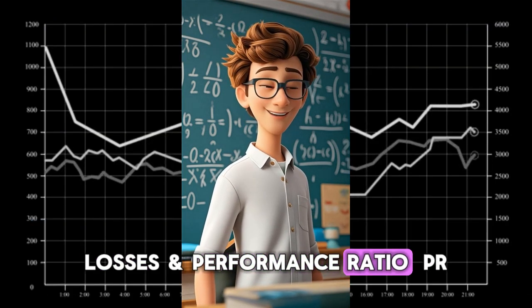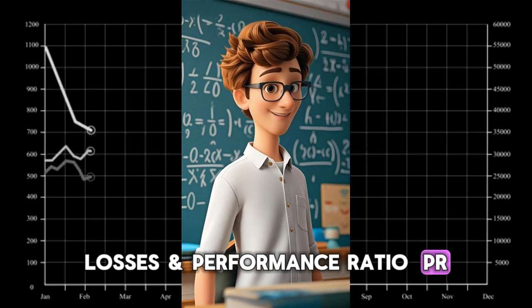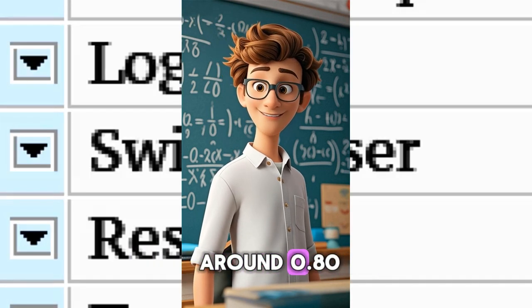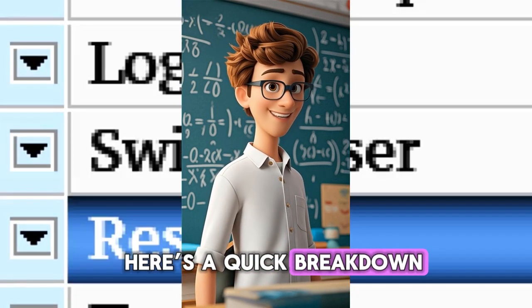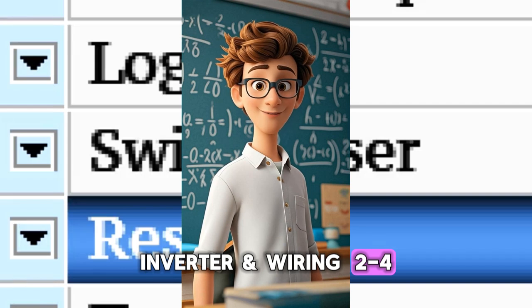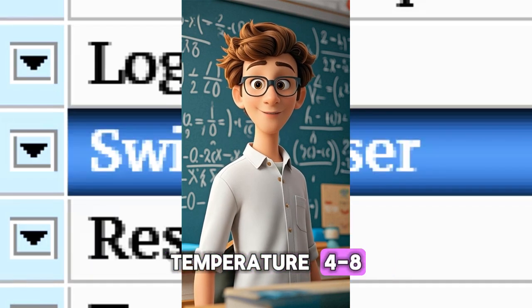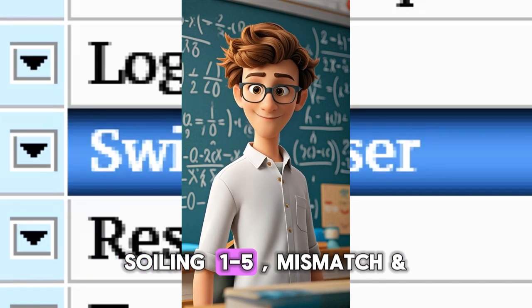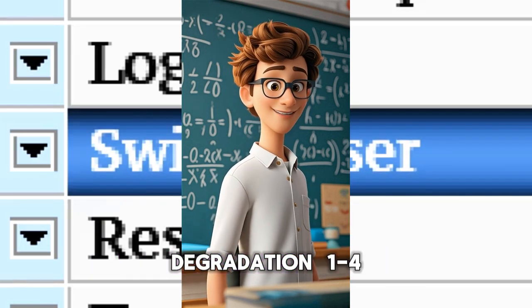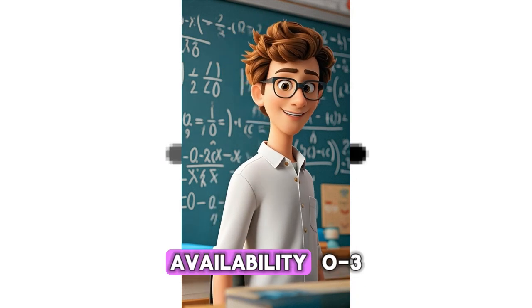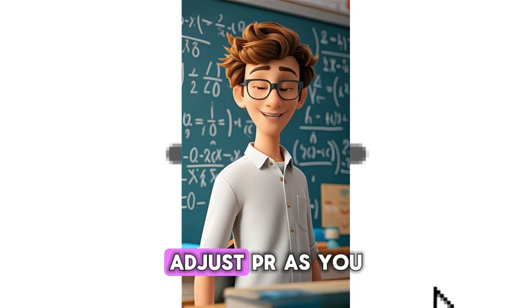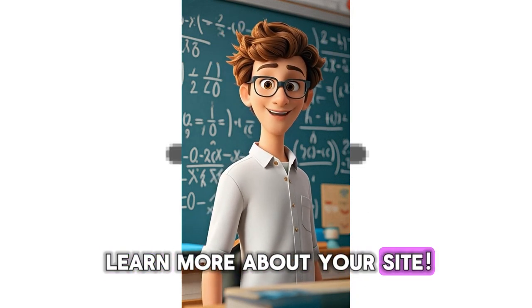Losses and performance ratio, PR. Typical first-pass PR is around 0.80. Here's a quick breakdown. Inverter and wiring, 2 to 4%, temperature, 4 to 8%, soiling, 1 to 5%, mismatch and degradation, 1 to 4%, availability, 0 to 3%. Adjust PR as you learn more about your site.